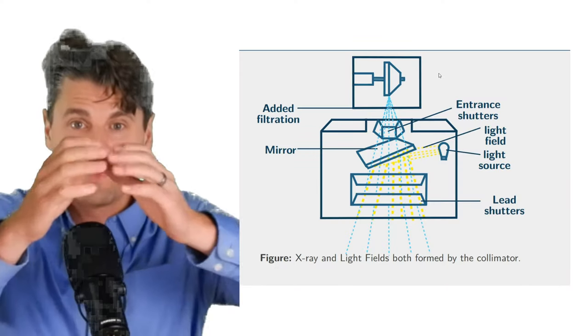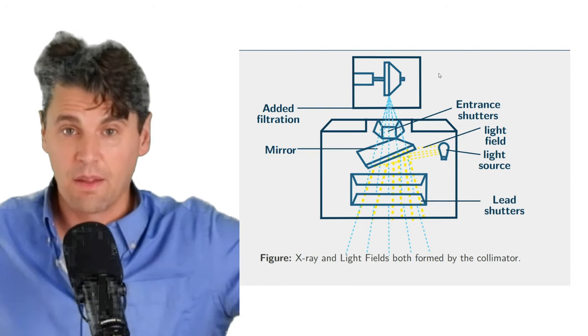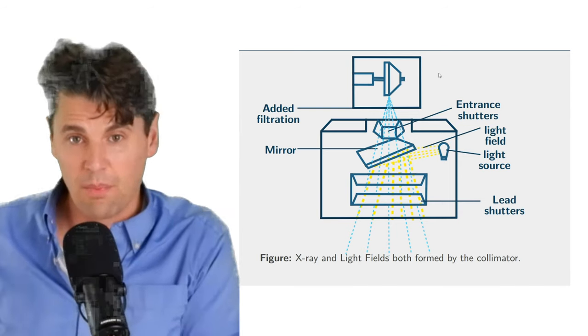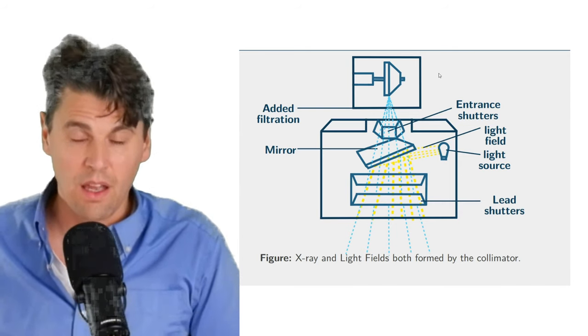An interesting idea is actually to use a light bulb so that we could visualize the x-rays coming down. But before the x-rays come down, we'll send light down, and the light field where that light field is landing on the patient, that is going to be coincident with where the x-rays are going to land on the patient.